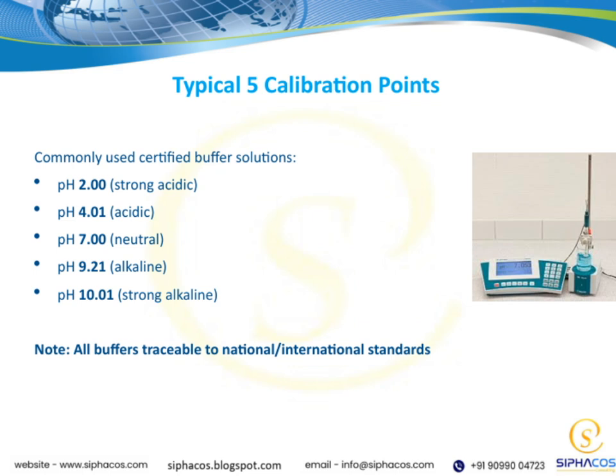Firstly, we have pH 2, which is a strongly acidic solution. It's useful when you're working with highly acidic samples. Next is pH 4.01, which is acidic but less extreme, often used as a mid-range buffer. Moving to the neutral point, we have pH 7, which is essentially pure water under standard conditions. It's a critical reference point in many measurements. Then, we have pH 9.21, which is alkaline or basic, common in various biological and environmental samples.